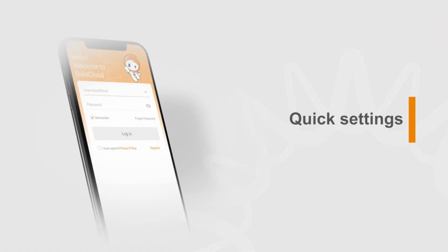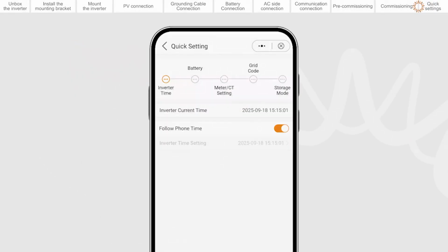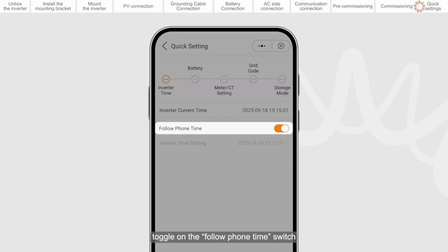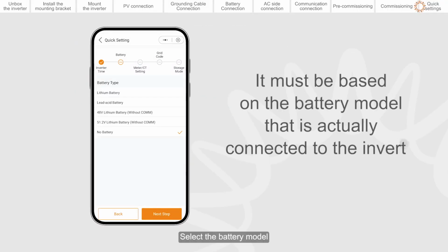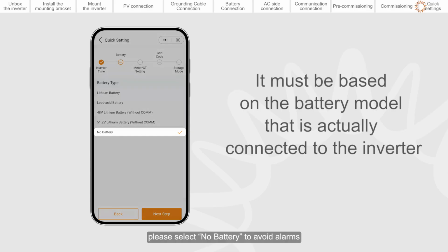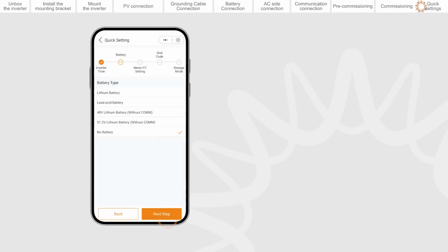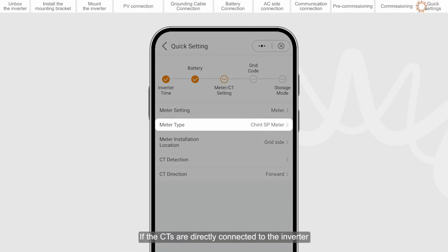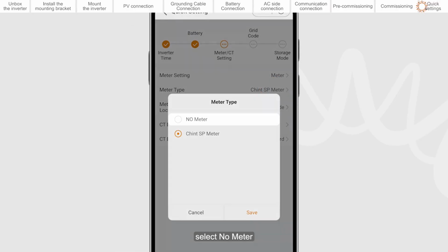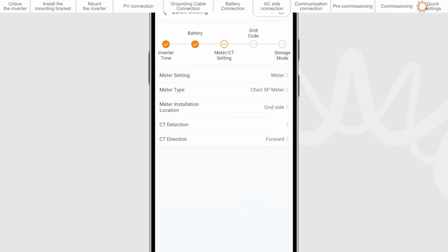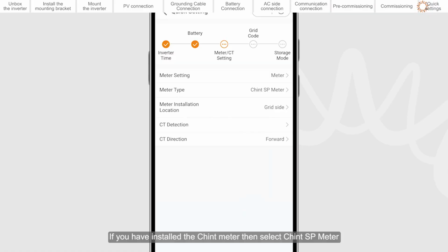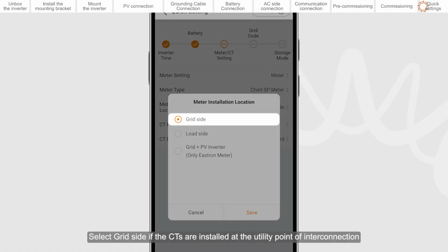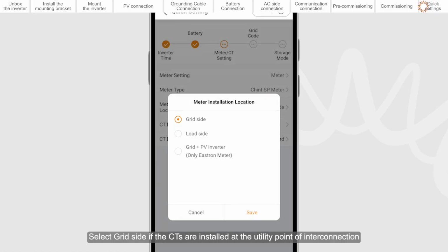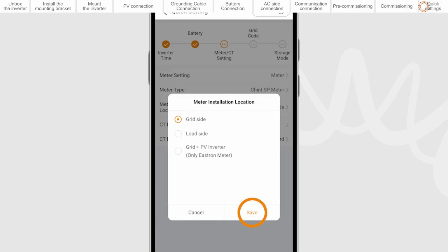Quick settings. To match the inverter date and time to your phone, toggle on the Follow Phone Time switch. Select the battery model. If there is no battery connected for the moment, please select No Battery to avoid alarms. If the CTs are directly connected to the inverter, select No Meter. If you have installed the Chint meter, then select Chint SP meter. Select Grid Side if the CTs are installed at the utility point of interconnection.